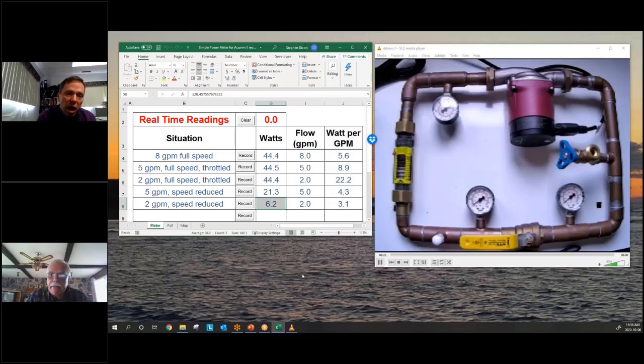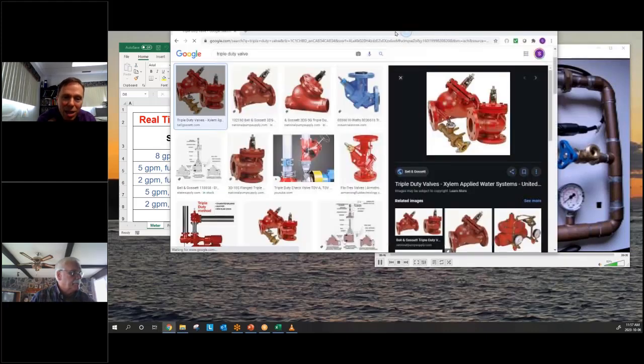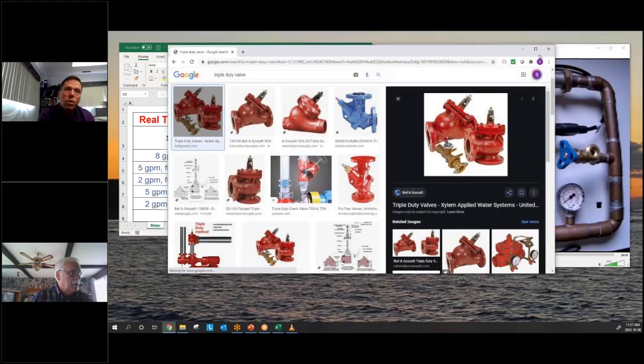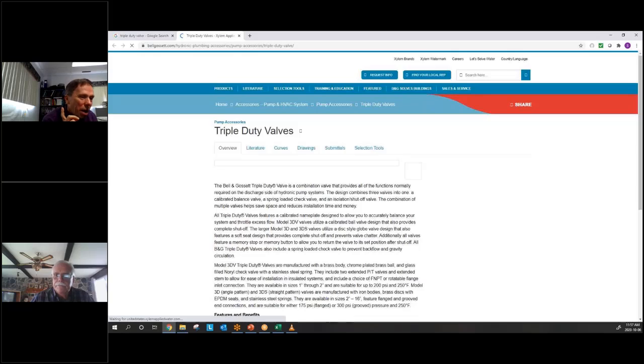The triple duty valve, I don't have a picture here. If you've never seen it, typically it's a stem and you see rings on the stem. And the number of rings that you see typically relates to the size of the valve. If you know it's a 4-inch or a 6 or 8-inch valve, you'll know how many rings you should be seeing. And again, make sure that it's completely open. If it's not, mark it where it is right now, take a wrench and see if it opens up. If it opens up, it means it's throttled. And the reason I say mark it is because you want to bring it back to where it was. Don't do any kind of test without being able to bring it back where it was.